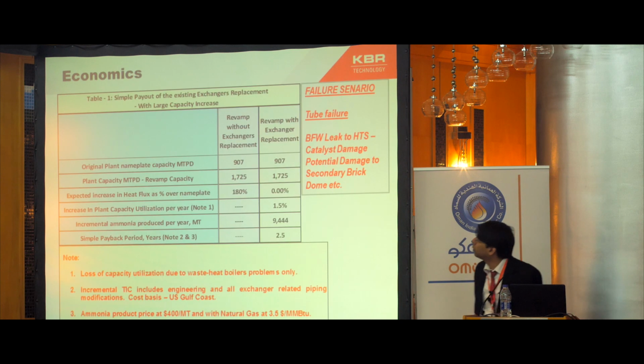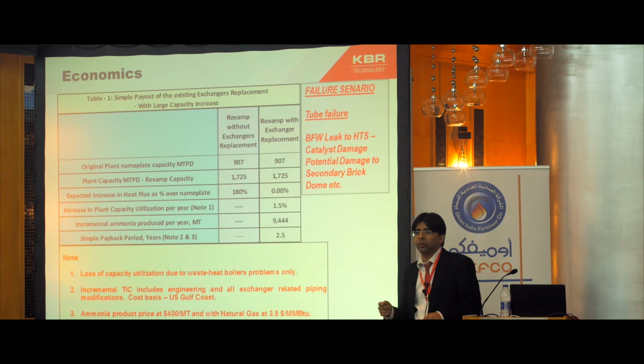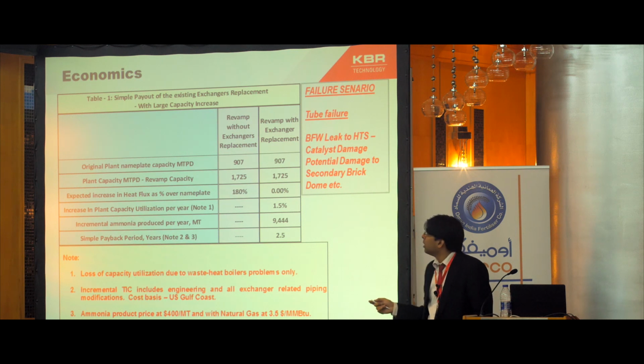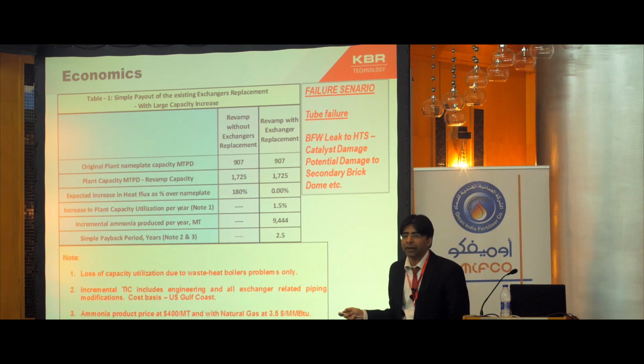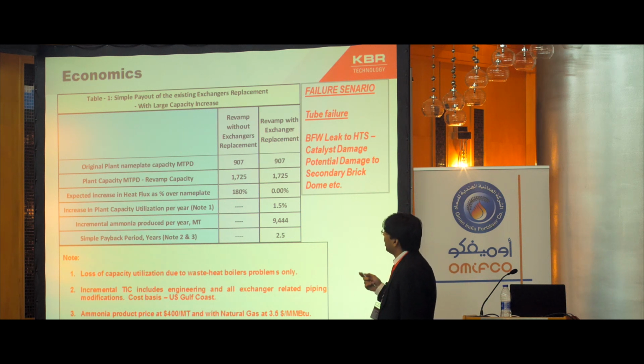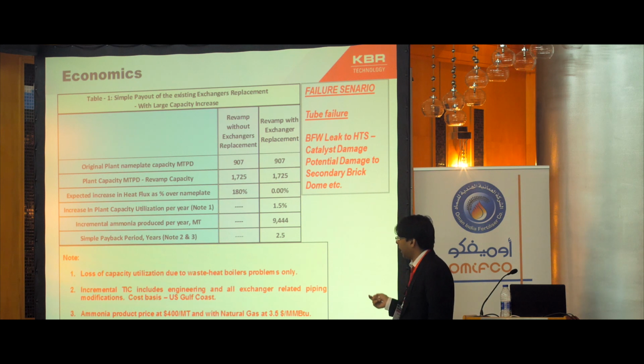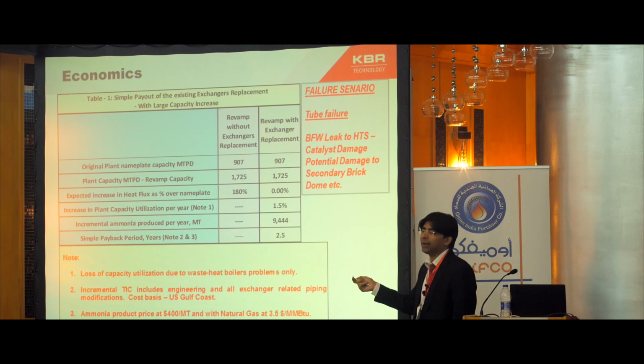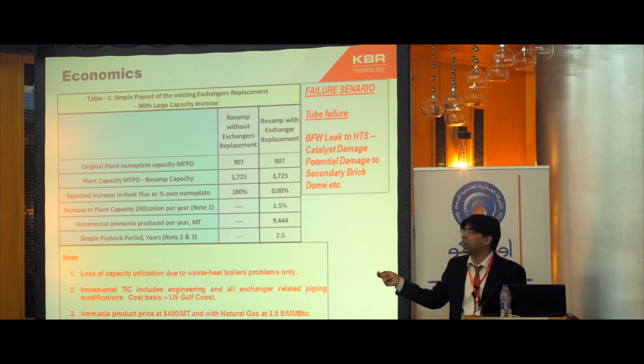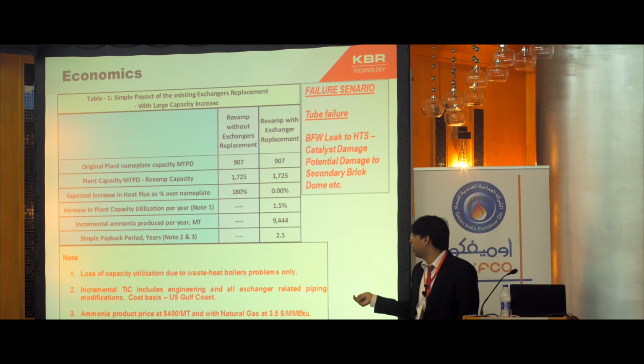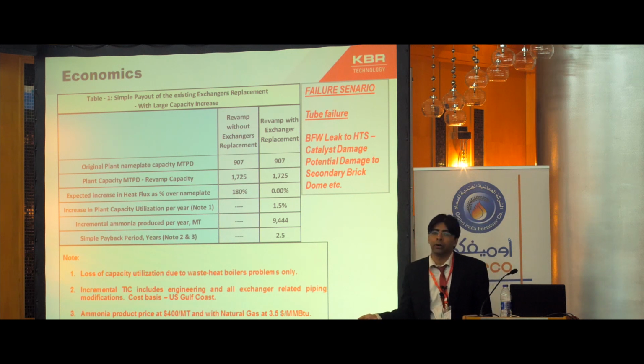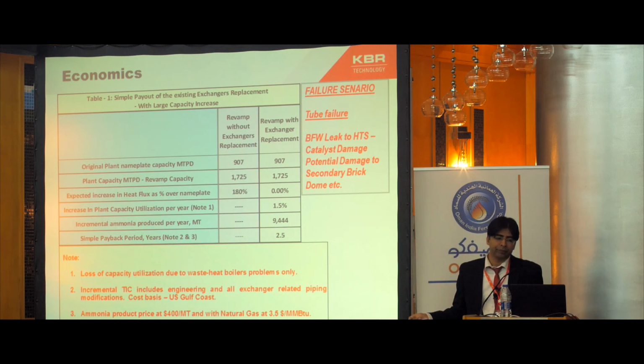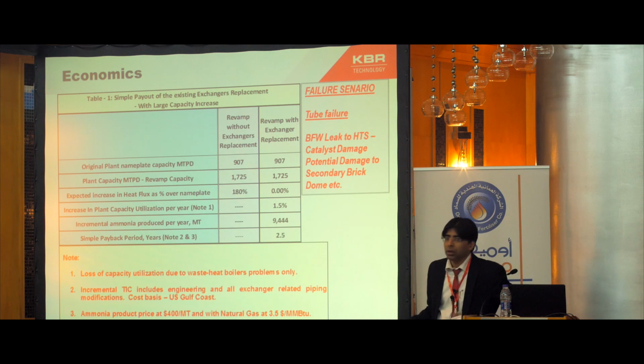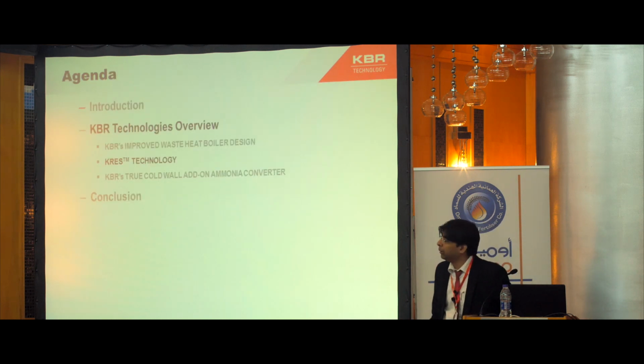So how does the economics work out? With the increase in reliability of the boiler, we can increase the on-stream factor by approximately 1.5% per year, which can lead to incremental ammonia production. The payback calculated is around 2.5 years, based on an NG price of $3.5 and an ammonia product price of $400 per metric ton. This is about the KBR waste heat boiler. If there are any questions.